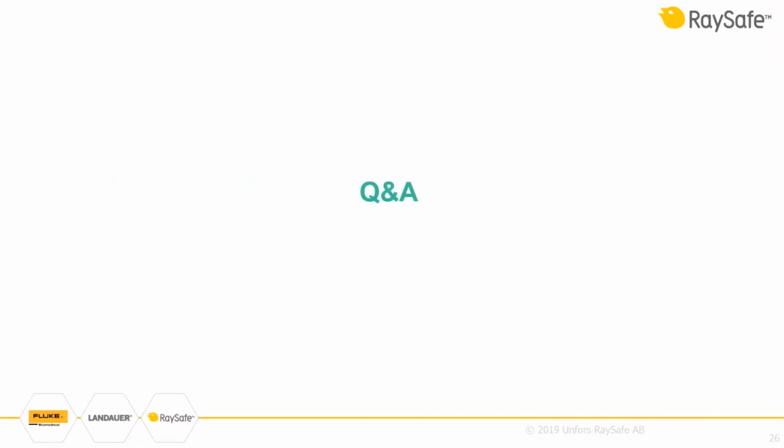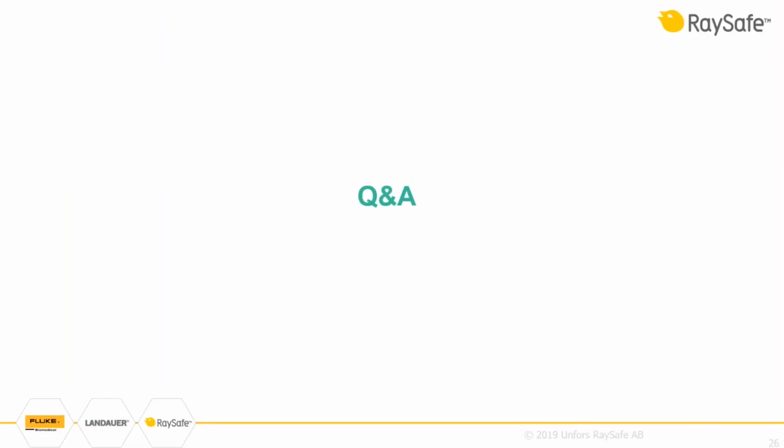Next question, it just says dead time is built in the survey meter. I don't know if you can interpret that a little bit? I could guess that, yes, we perform dead time correction with the survey meter 1,000 times per second, actually. So we do that a lot to make sure that we get as good dose rates as possible. We also got a comment here that it may be helpful to state that if you do not purchase the full kit with both lids, you cannot utilize it without the lids for counts.